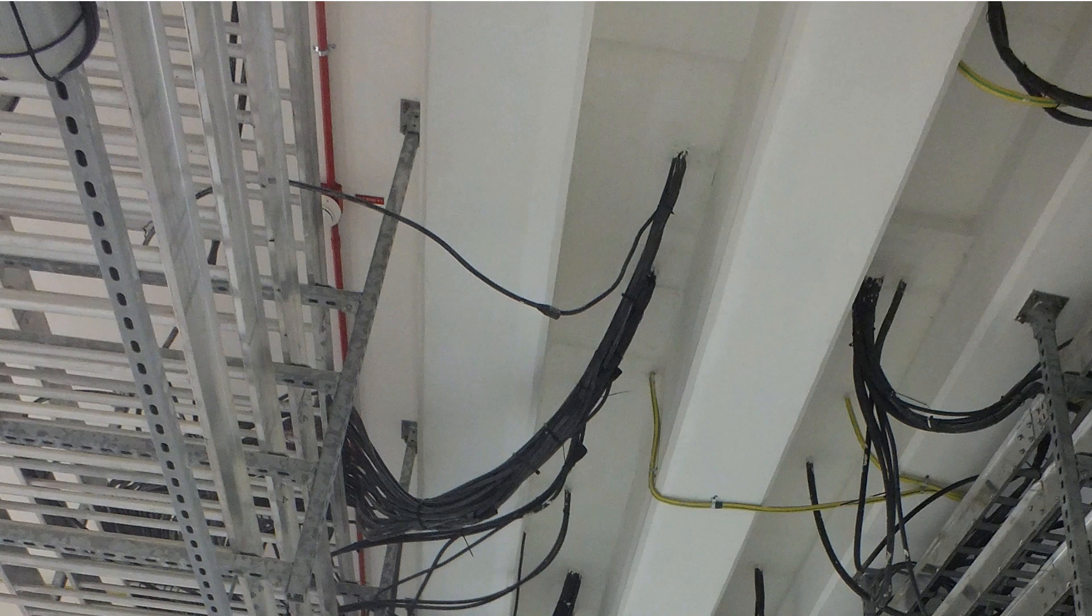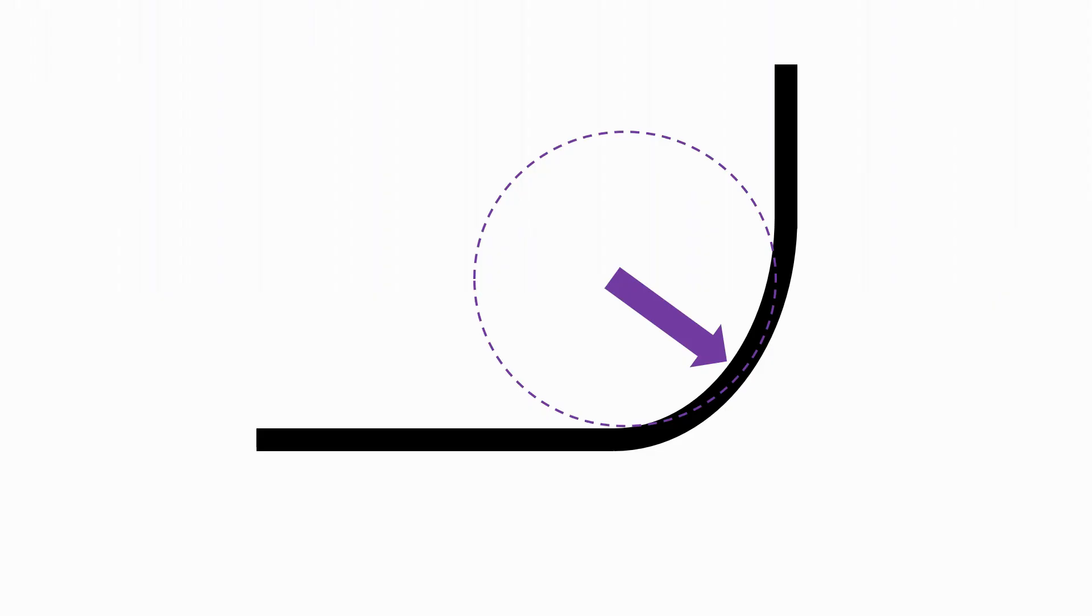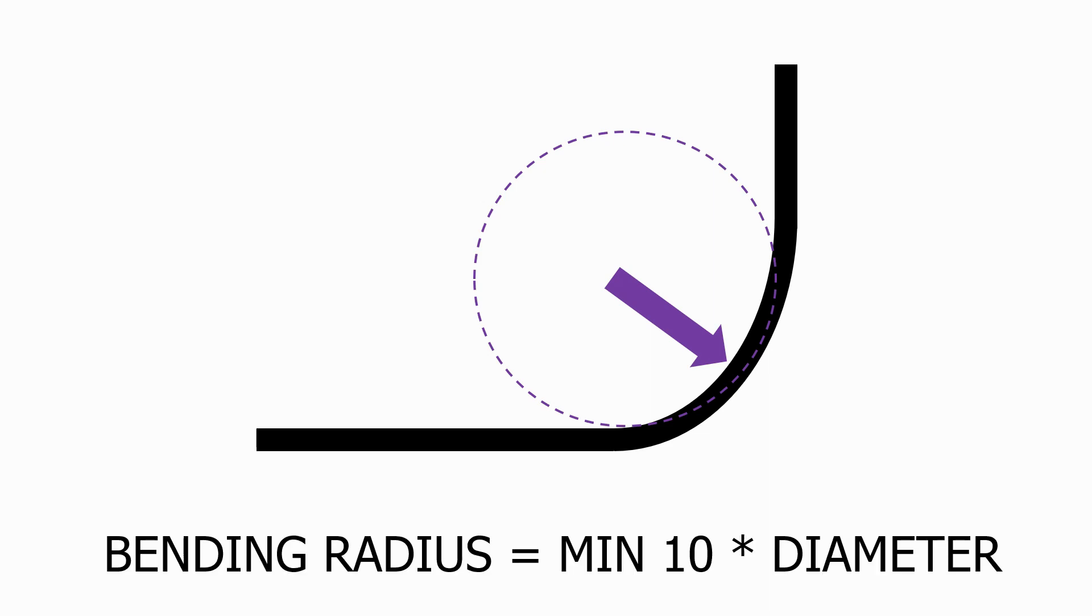When we're designing the cable tray system we need to ensure that we don't put the cable tray too close to the bottom of the panel as we need to consider the bending radius for all of the cables involved. This is defined by the manufacturer and the minimum distance that we need from the cable tray to the bottom of the gland plate will be defined by the cable that has the largest bending radius.